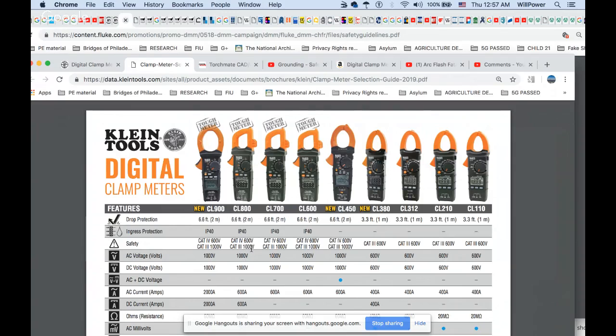you do not use this tester because it might be over 600 volts and the protection is lost at that point. As you can see, they're at 600 all the way across under Cat 4, but they'll give you Cat 3 at 1000 volts. So if the panel is where you're working, it's going to be a different rating now. It's not that this gives you 1000 volts protection.